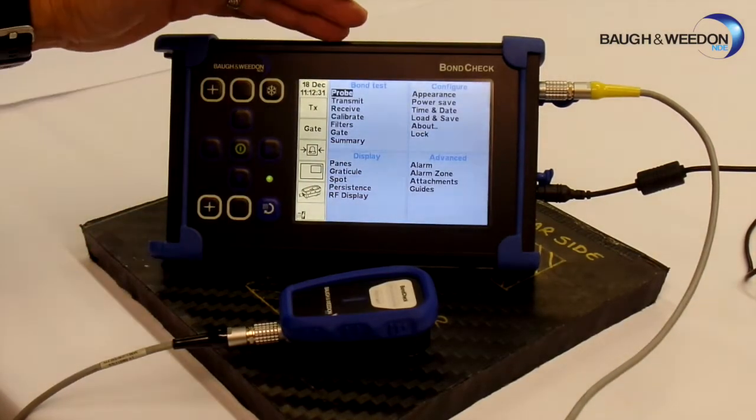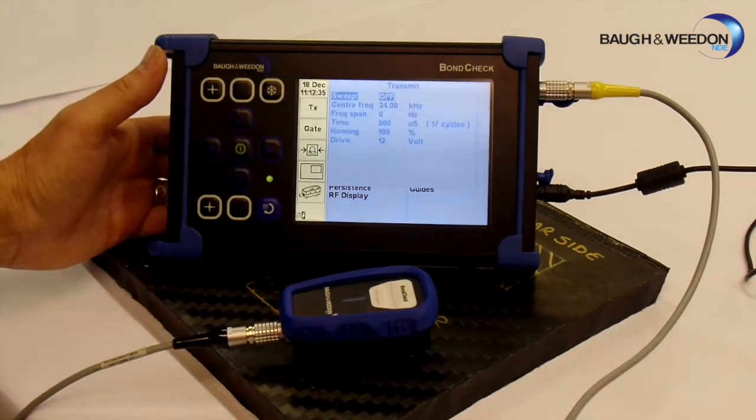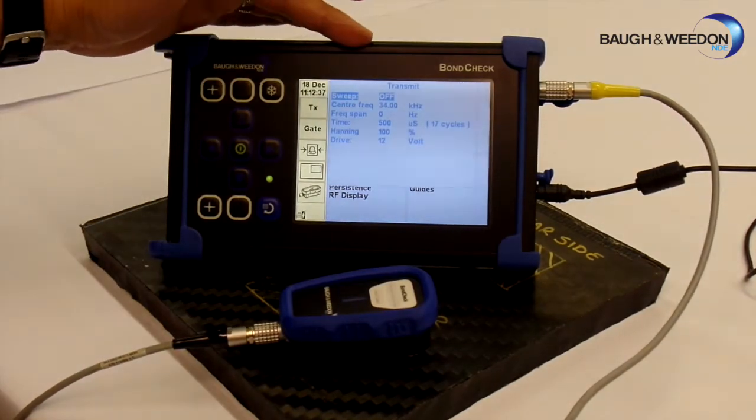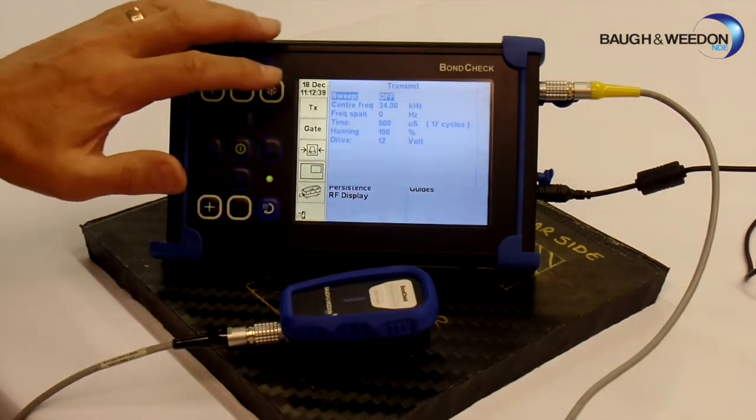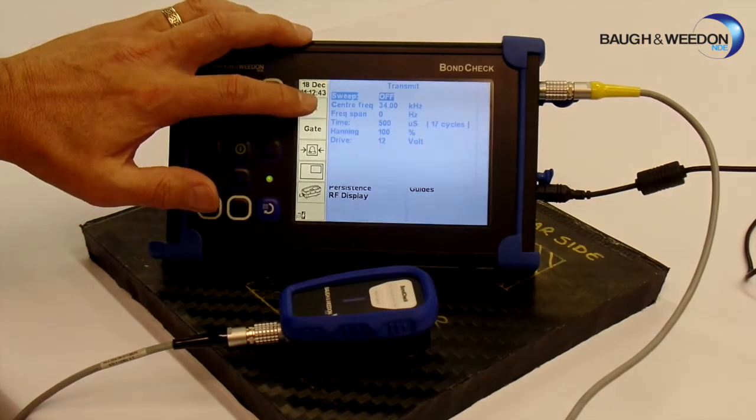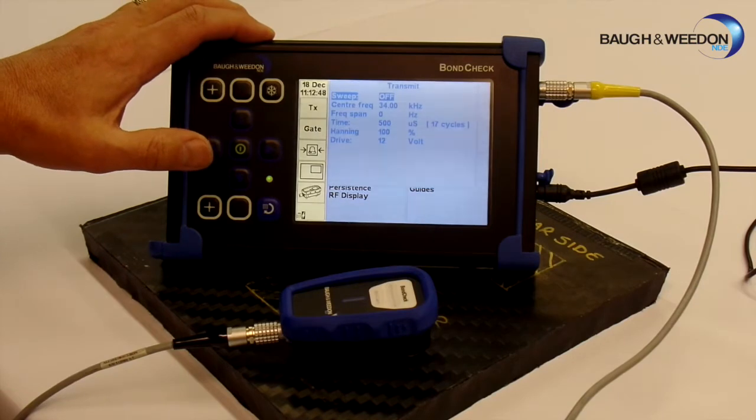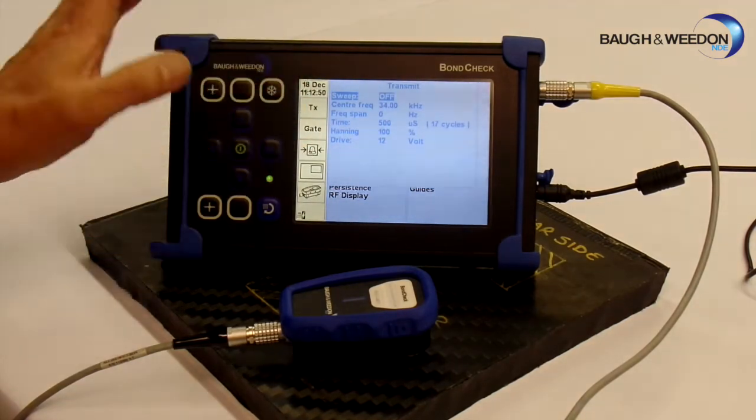We have been in probe, we are going to transmit next. Sweep is off, which is what we want for the calibration for the inspection. The center frequency of this probe is around about 34 kHz, that is correct. Everything else is okay.